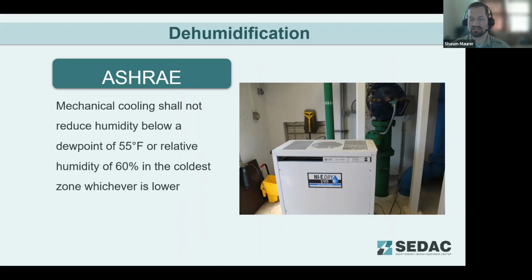This can be a very energy intense process, so it's good to understand why it's required and how tight that tolerance is. Commonly, the goal for relative humidity is to keep it between 40 and 60%. In the wintertime, though, it's commonly below this range and humidification equipment is required. And so this standard is trying to incorporate that where the IECC doesn't really have this requirement. It allows buildings to dry out a bit more and doesn't really reflect, if you do install a humidification system, the limitations on controls. It kind of leaves that to the designers to build that into the controls.